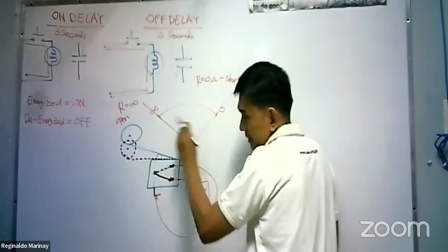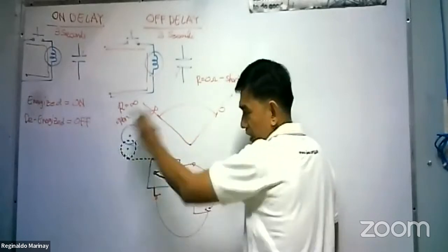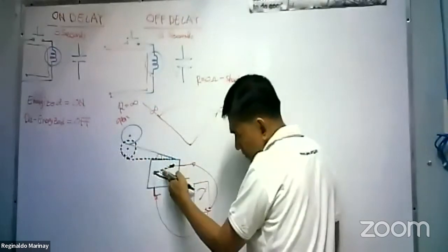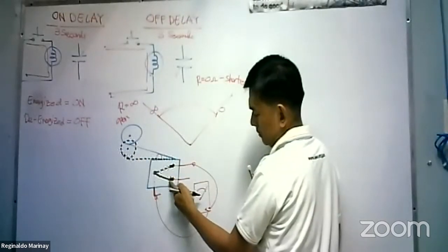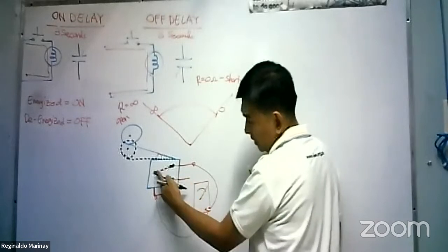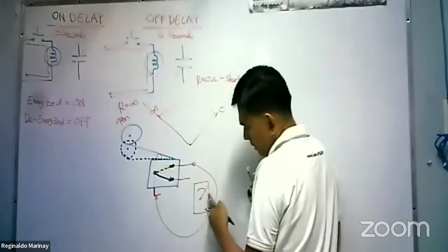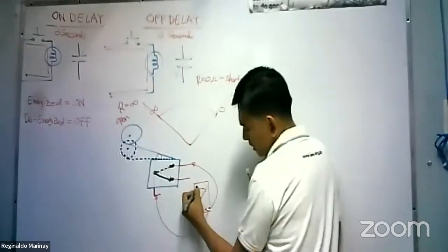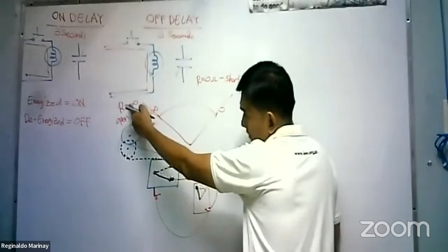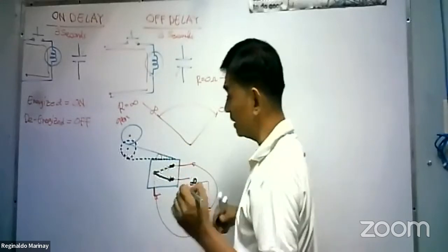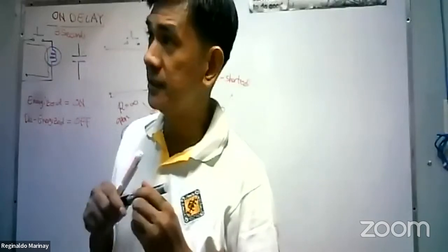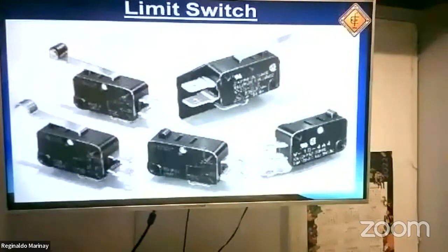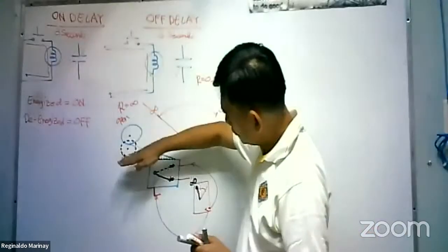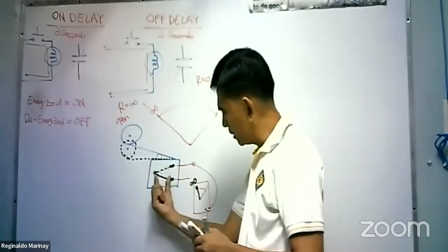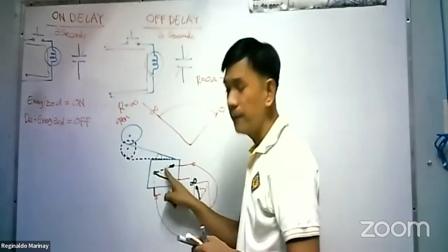When this wheel is in contact with another object or another body, this will go down, this will become open, and this will become closed. Of course, if this becomes open circuit already, this will go back to original position, which is, that is open. Again, that should be infinite resistance. That will be infinite resistance. That's the difference. That is a limit switch. Then of course, it will go to the original position. Okay? This will go back to original position here. This will become closed. Okay? That is a limit switch.